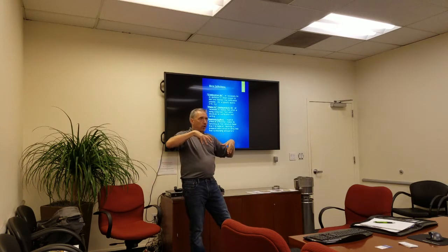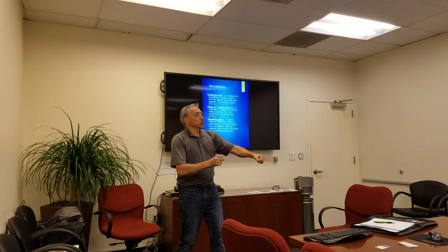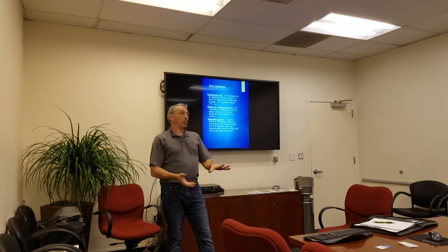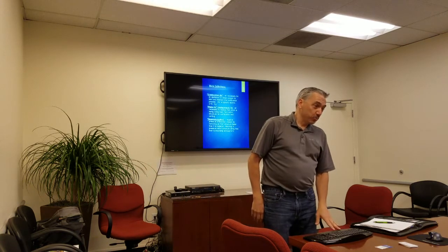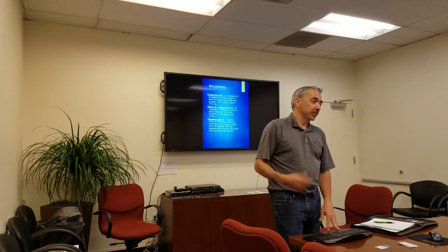It's possible to establish enough draft that our room becomes depressurized, or at a negative pressure. You can tell that if you open a door and the air is kind of sucking on it. So if you're opening your boiler room door and it's trying to be sucked closed, there probably is insufficient makeup air to that room. And what sometimes happens is they'll just prop the door open to make the appliance work because it doesn't burn really well if they close the door. But anyway.